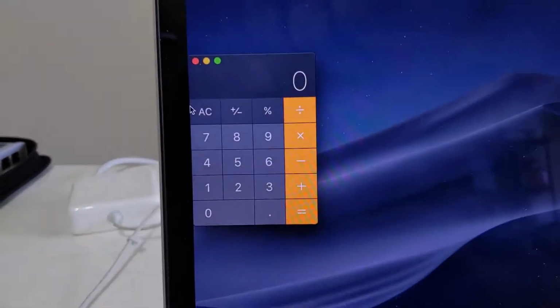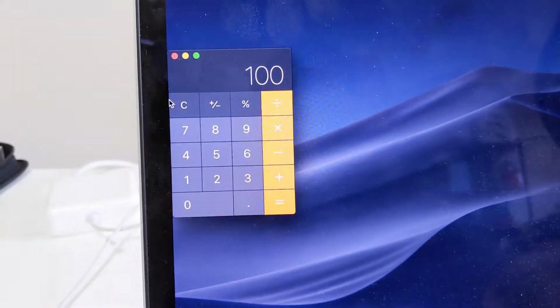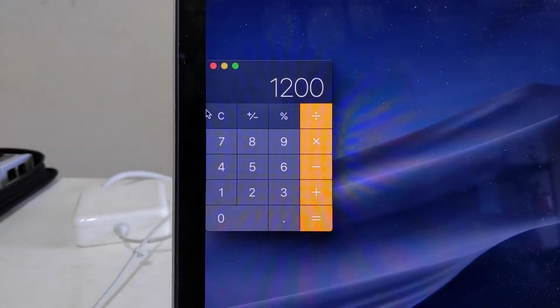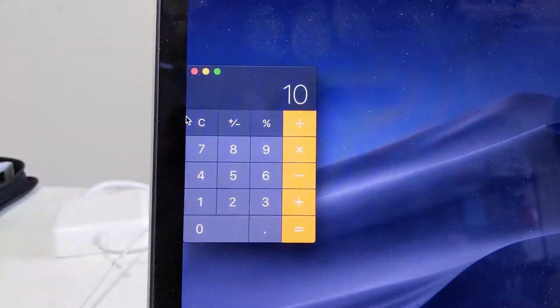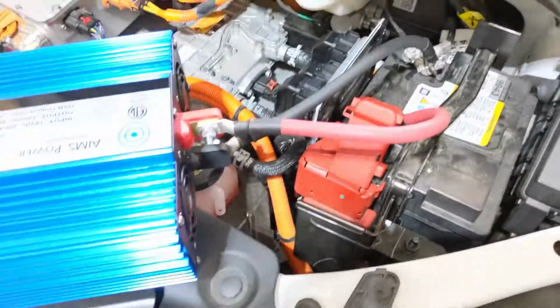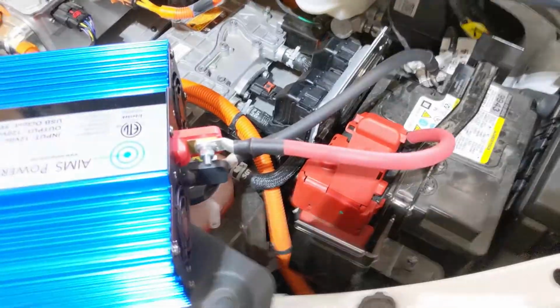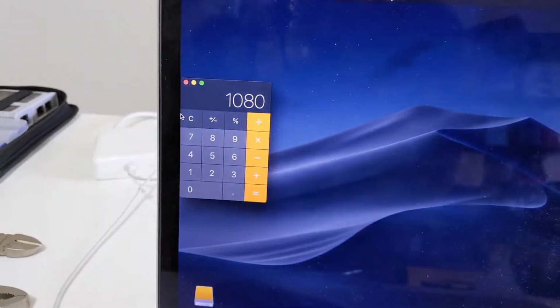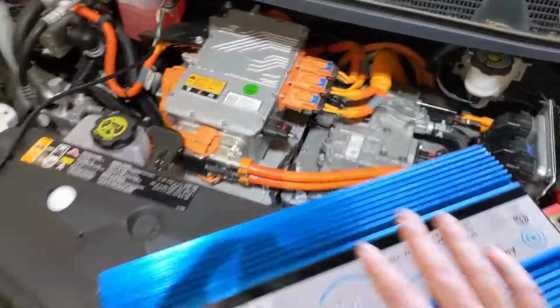So if we take our 100 amp limit on the DC side and do a little calculation here, we say 100 amps times 12 volts, 1200 watts, and then if we divide that on the AC side by 120 volts, it gives us about 10 amps that we can safely pull from this whole system here. So maybe subtract 10% from that, just from losses and a safety factor. And we could probably pull about 9 amps total on this system for a total of about 1,000 watts, which is a good rule of thumb to use on this system. Nothing will get hot, and our cabling will be fine.